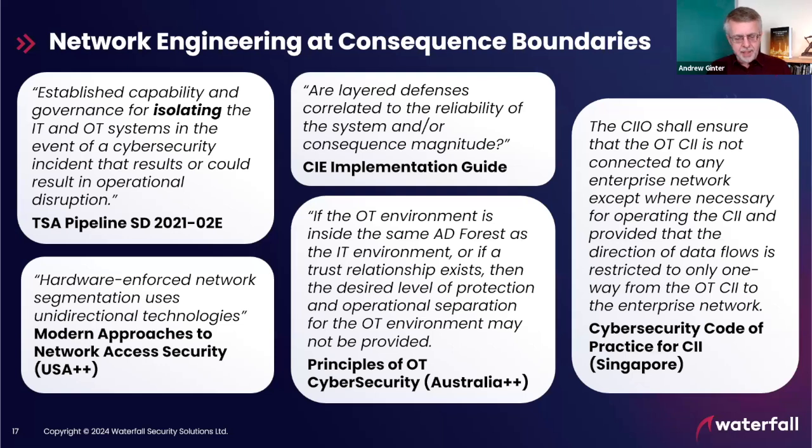Why? Because that overpressure relief valve is our last ditch defense. We had 4 levels of digital safety break before the mechanical valve engaged. This should never happen. When that valve engages, 9 times out of 10, the operator lifts the cage on the big red mushroom button, shuts down the plant, because we need to find out what just happened here. How did that happen? Why did that happen? And what are we going to do to make sure this never happens again? We were this close to dying.